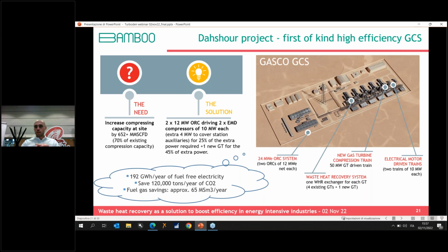This is an existing gas compressor station that a few years ago was identified to be upgraded, let's say, to increase the pumping capacity of gas throughout the facility. In this case, instead of adding new open cycle gas turbines to pump the additional gas to the pipeline, the customer has decided to install Organic Rankine Cycle to do waste heat recovery on the existing gas turbines, and with the power produced, basically drive two electric motor driven compressors that in fact added the new capacity to the station. So in this case, the project is quite big because we are supplying two 12 megawatt each Organic Rankine Cycle turbines.